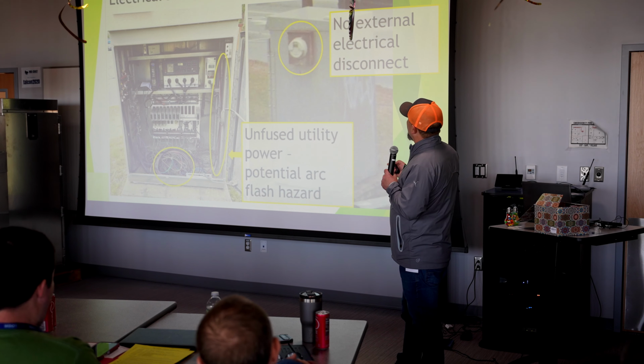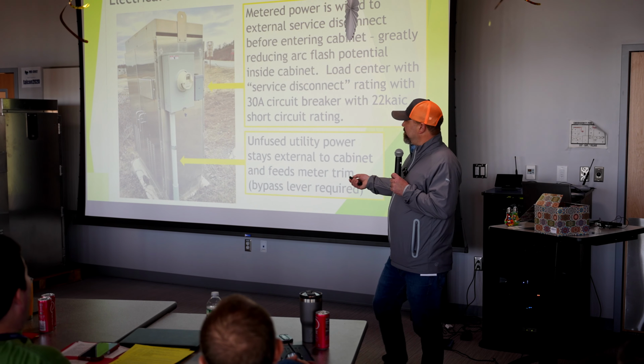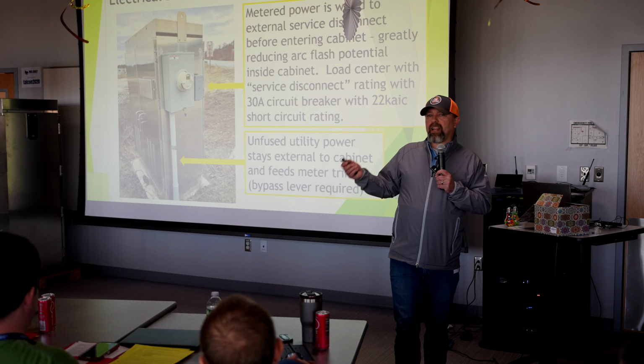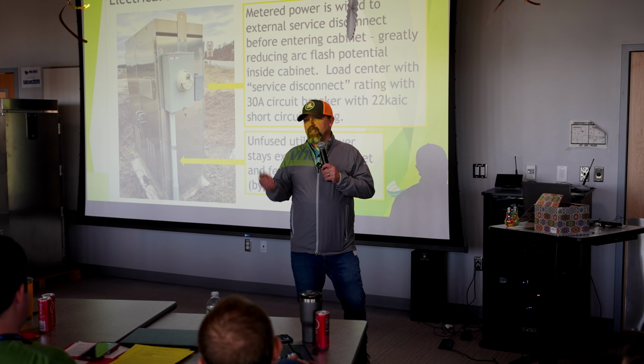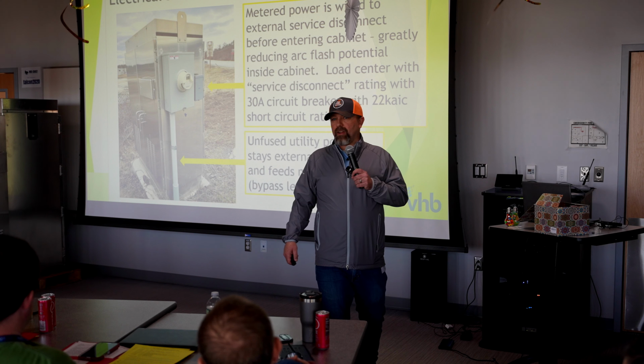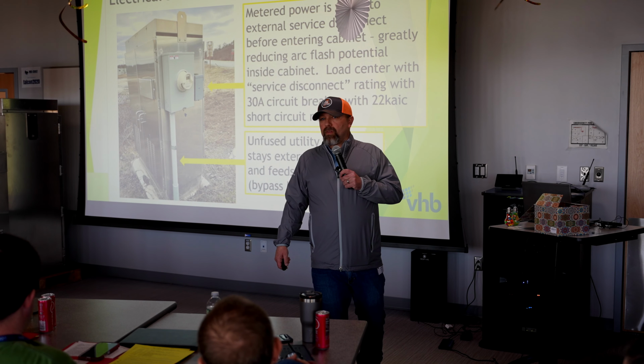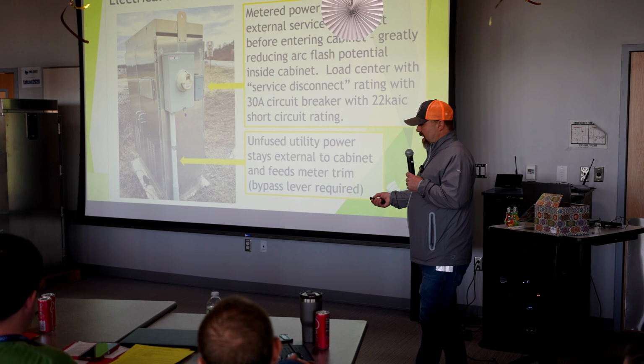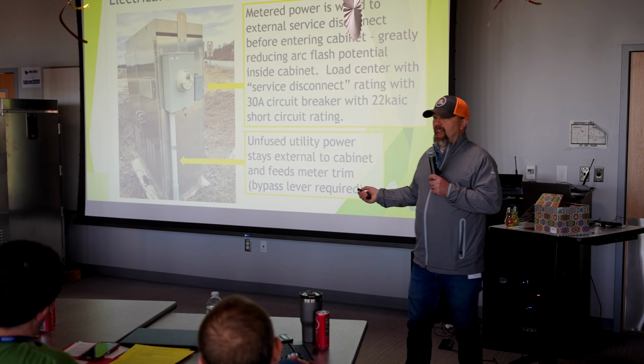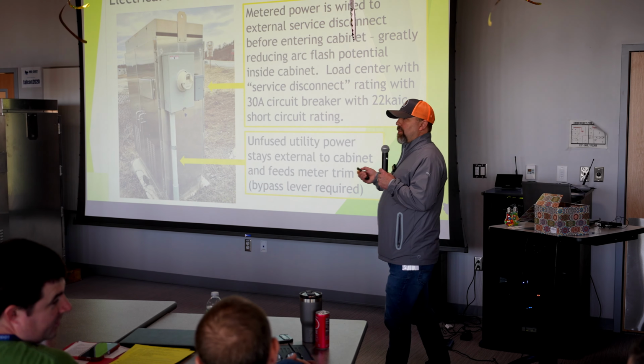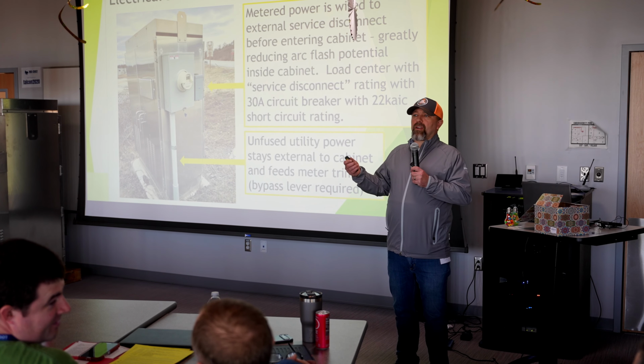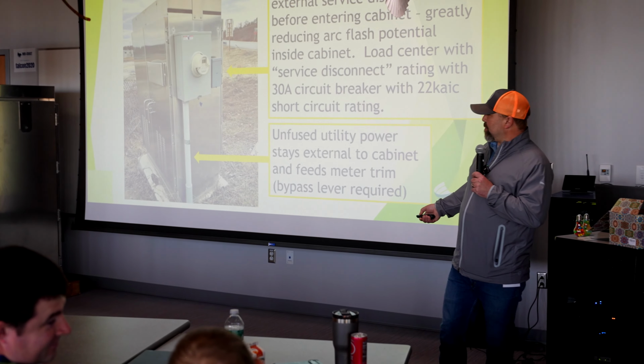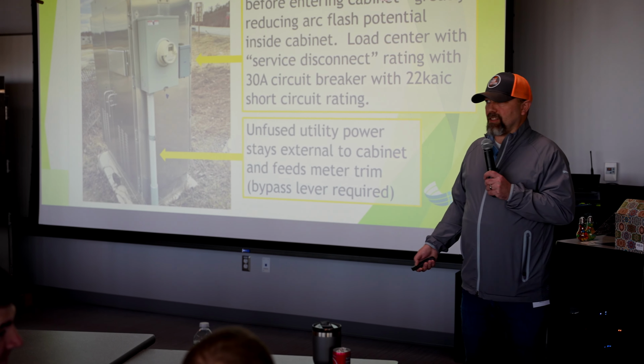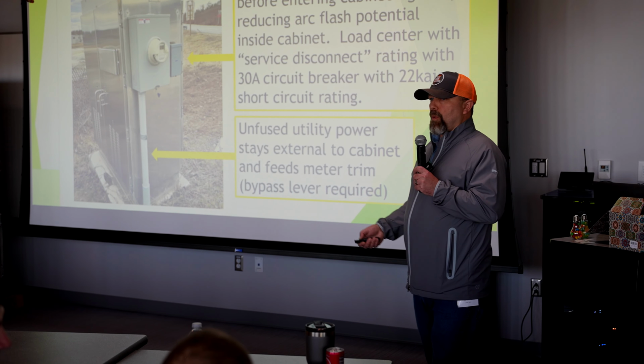So in order to do that, what they would like to see, and I don't know, Kurt, if this is in the standard details or if we're planning on adding that. That is being updated? Okay. So to get around that arc flash potential, they want to start running the utility conduit on the outside of the cabinet. Now, there are still installations taking place like the old way, and it's not like it's a huge crime, but it's what we want to get away from.